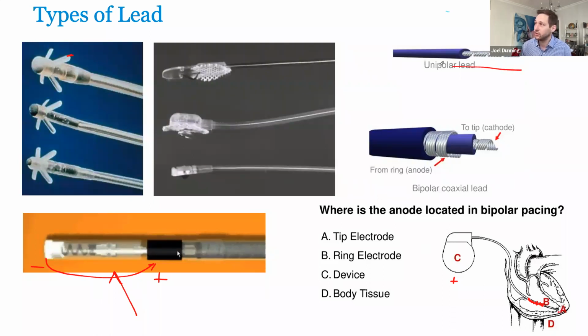In a unipolar lead, you can see here, it's much simpler, just a single core, versus the modern bipolar. They used to be side by side. Now they wrap the ring electrode around the outside, separated by an insulator right here. It's interesting to see that the anode, the ring electrode, is actually more exposed in some sense. It has less insulation. So typically when you see modern bipolar leads failing, it's the ring electrode that is failing. In those cases, you can program unipolar to circumvent the part that could be failing, which we'll get to later on.